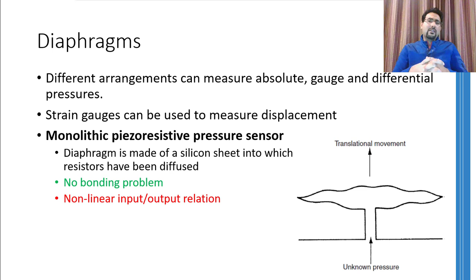If you can remember, in our discussion on strain gauges, I said that a major problem in the use of strain gauges is to attach or bond them onto the material of which you want to measure the strain in a very definitive direction. If the strain gauge is not attached in the right or active direction, it will be of no use. So as the diaphragm expands, the resistors will expand with the diaphragm and there is a resistance change that can be measured easily. The only problem associated with these kinds of pressure sensors is that their response is quite nonlinear.